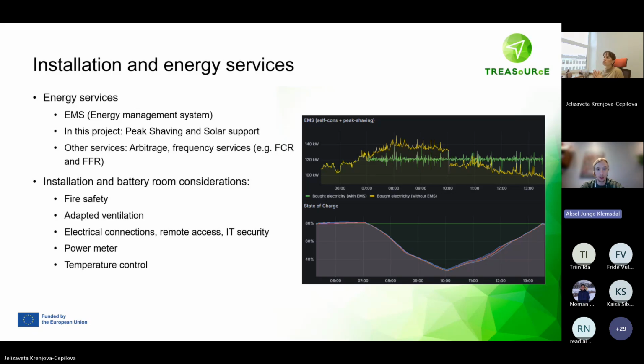In this project, we have done peak shaving and solar support. On the right is a picture from one of the demo sites doing peak shaving—the green line shows building consumption with the battery system, the yellow line without. As consumption increases, the battery takes over, creating a fixed line around 120 kilowatts, which would have been 140 without the battery system.